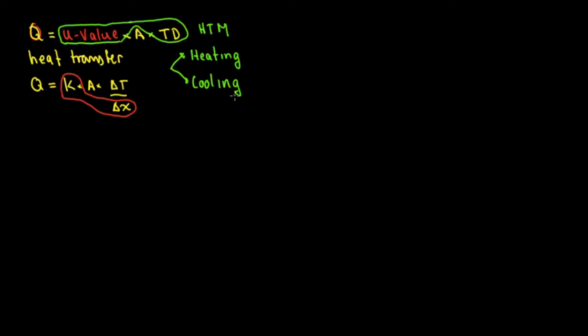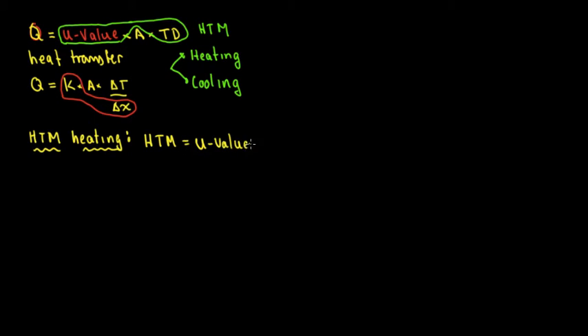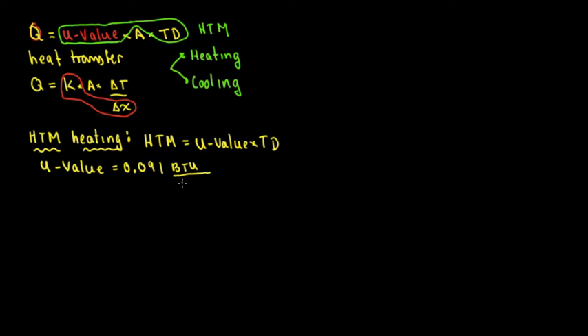Let's continue with this calculation. The heat transfer multiplier for heating is pretty much the same equation: heat transfer multiplier equals the U value times TD. For example, the U value depends on the construction. If the U value equals 0.091, the units are BTUs divided by hour, square feet, and Fahrenheit.